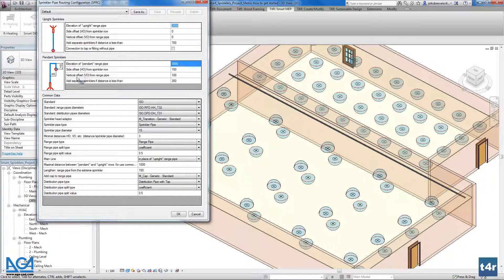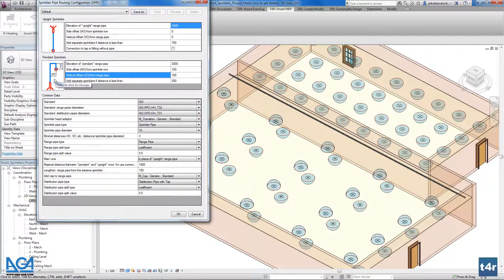The second thing is the side offset and the vertical offset, marked on the image. That means how far the sprinkler will be from the pipe. We also have the functionality to add a separate sprinkler pipe if the distance is less than the entry distance — meaning a separate pipe is added to a sprinkler if the distance between the main row and the sprinkler is less than that value. We can also choose to connect or not connect to a tap or fitting, which allows you to connect the sprinkler directly to a tap or fitting, for example Blazemaster fittings.